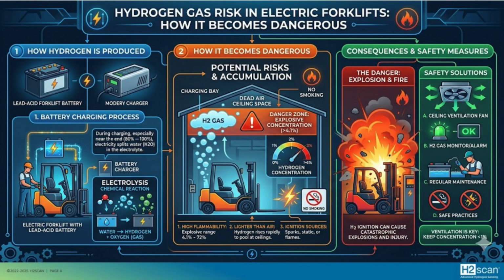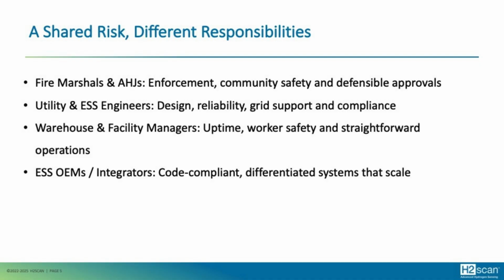Make sure they're topped up with water, because if they're not properly maintained, as the plates are exposed to air, they will create more hydrogen gas. And so also safe practices, making sure you have the correct safety signs in place and the correct training for your personnel, and making sure that no open flames or smoking or anything happens inside of these areas. So this is a shared risk and responsibility. So you're an owner or an operator or a facility manager, you're responsible for what I just described, making sure your facility is set up to mitigate the hydrogen in the room.